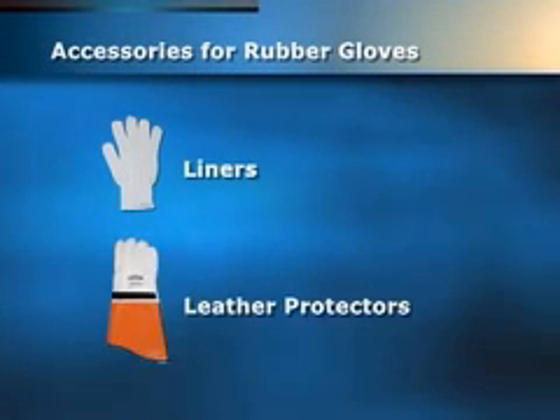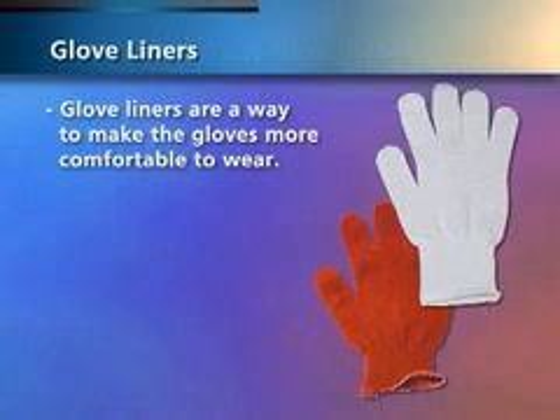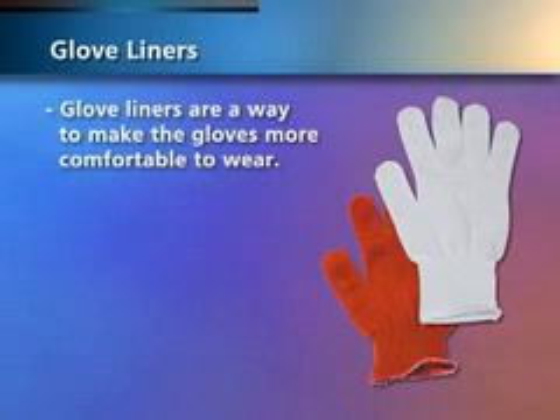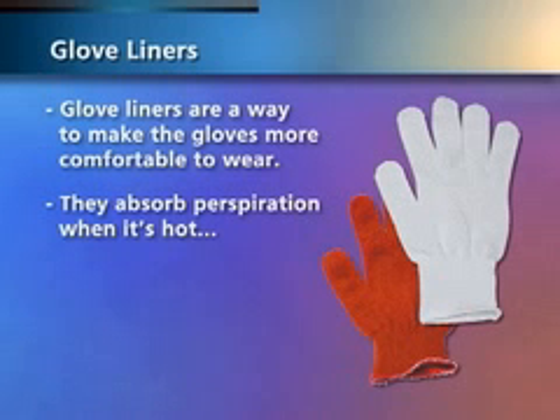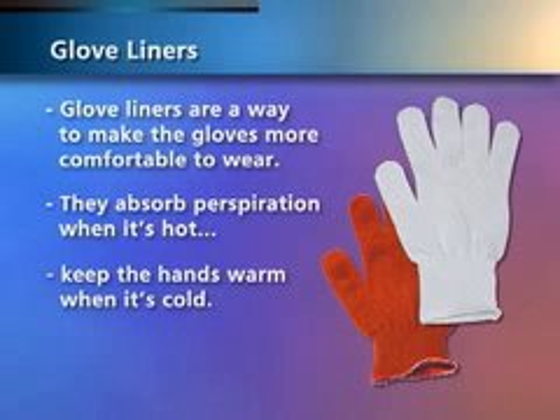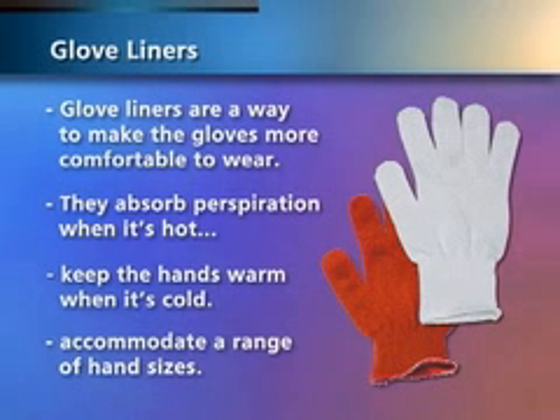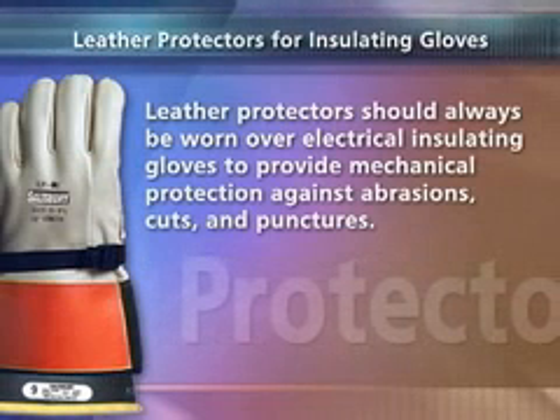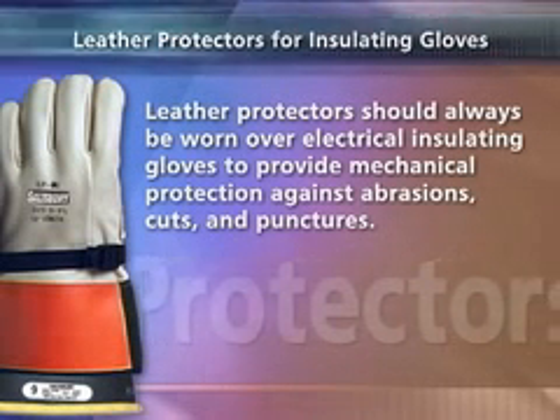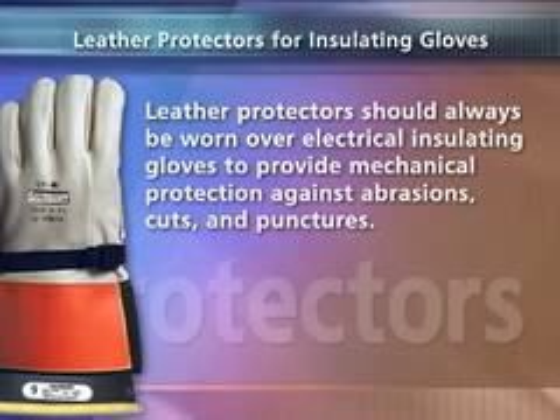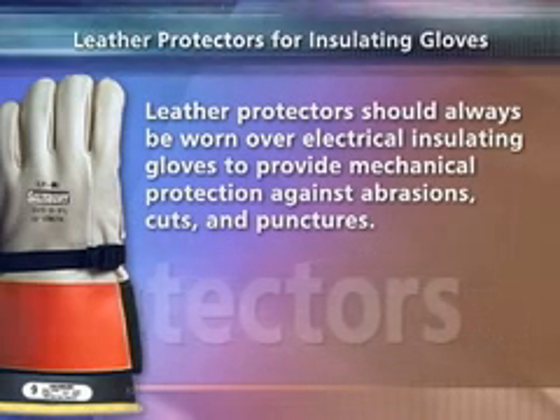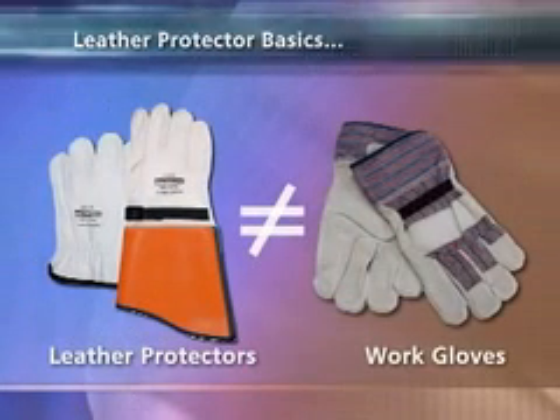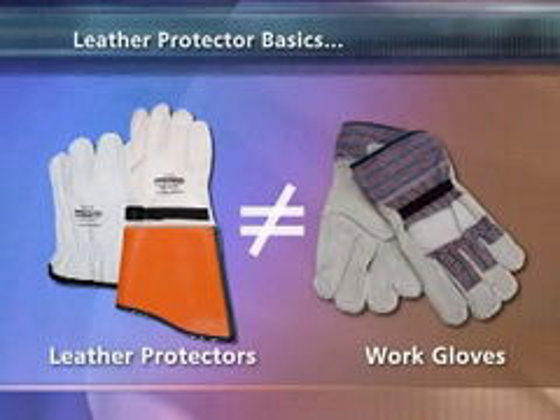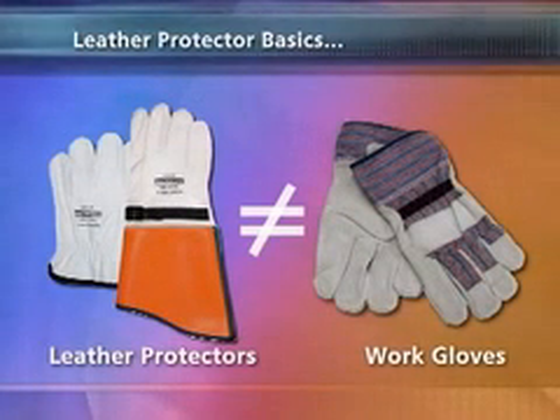Two important accessories for rubber gloves are liners and leather protectors. Glove liners are a way to make the gloves more comfortable to wear. They absorb perspiration when it's hot and keep the hands warm when it's cold. Glove liners are made from absorbent fabric and accommodate a range of hand sizes. Leather protectors should always be worn over electrical insulating gloves to provide needed mechanical protection against abrasions, cuts, and punctures. Leather protectors should never be used as work gloves, and work gloves should never be used as leather protectors.